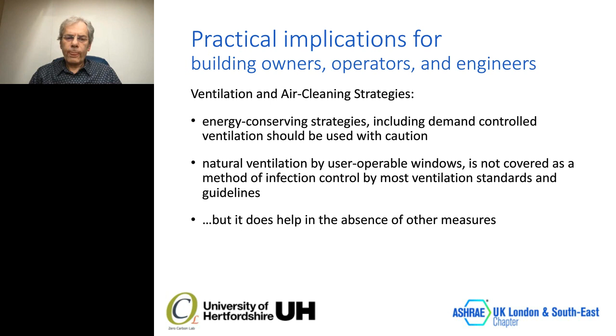We also need to consider room pressure differentials, as these are important for controlling airflow between areas in a building. For airborne infections, we need to put these rooms on a slightly negative pressure with respect to the surrounding areas. And we are talking only a few pascals of difference. And in hospital rooms with immune compromised individuals who have weakened immune systems, these rooms need to be kept at positive pressure in protective environments. And I'll show how that works.